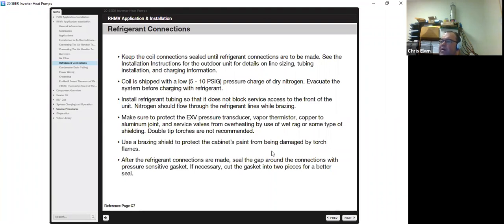After refrigerant connections are made, make sure you seal the gap around the connections with the pressure-sensitive gasket provided. If necessary, cut the gasket in 2 pieces for a better seal. Put them on there ahead of time, because they're going to melt.